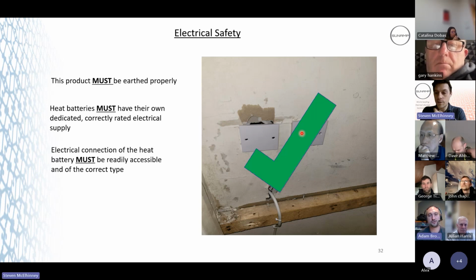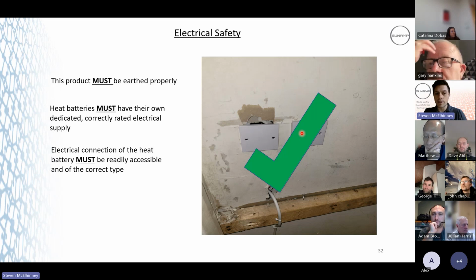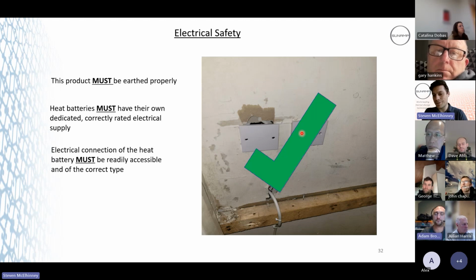Yeah. So, I'm struggling with the location. There isn't a socket anywhere near. I could possibly run a fused spur from it, but I was thinking that because it's only, I think it's 0.25 amps. It's tiny. Do you know what I mean? I wondered is that going to be okay? Yeah, that'll be fine as long as you're not going to exceed that 16 amp rating. No. I mean, the units themselves, they'll pull about 13 amps, maybe a little bit more depending on what the incoming voltage is to the property. So yeah, if you're going to add 0.25 amps, it's not going to make a difference, or 0.025. That's what I thought, but I just wanted to double check. Thank you. Yeah, that should be fine.